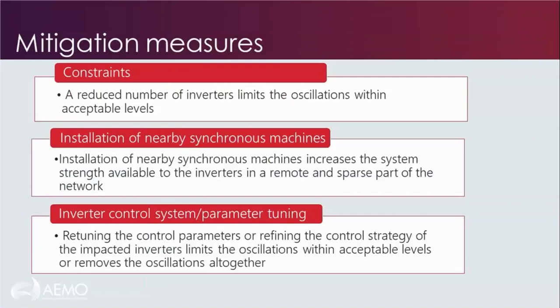Now that we have confirmed this problem is real and is not a modeling artifact, what solutions are available to us? We consider three mitigation options almost concurrently, but some of them would take longer to implement than others. The first one was the application of an operational constraint, which would limit the number of inverters for each inverter-based resource project that would otherwise be accepted to be online.